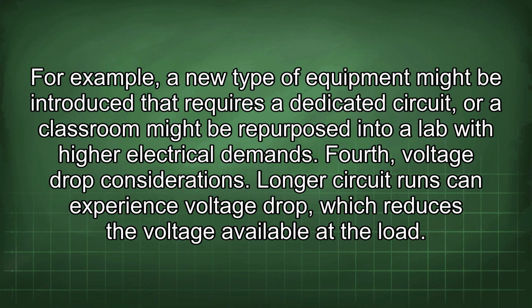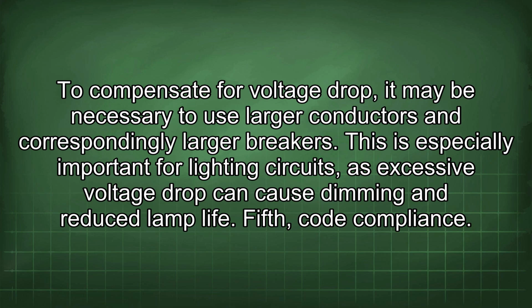Fourth, voltage drop considerations. Longer circuit runs can experience voltage drop, which reduces the voltage available at the load. To compensate for voltage drop, it may be necessary to use larger conductors and correspondingly larger breakers. This is especially important for lighting circuits, as excessive voltage drop can cause dimming and reduce lamp life.